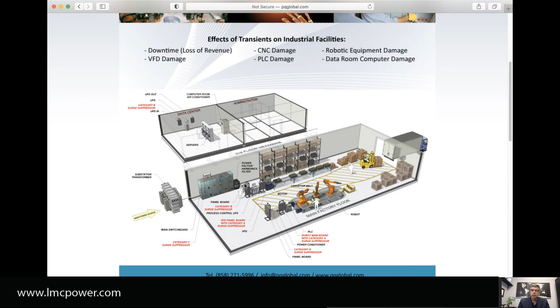So if you look at it, you have your category C, a surge protector at the input. Then you have a conveyor belt and a robotic line, both protected with category Bs. And the variable frequency drives here, very similar to the Heineken protection we did with the DIN surge filter, have category A. This facility also had a little mezzanine with a small computer room that had an air conditioner and a UPS, also protected with a category B protector.